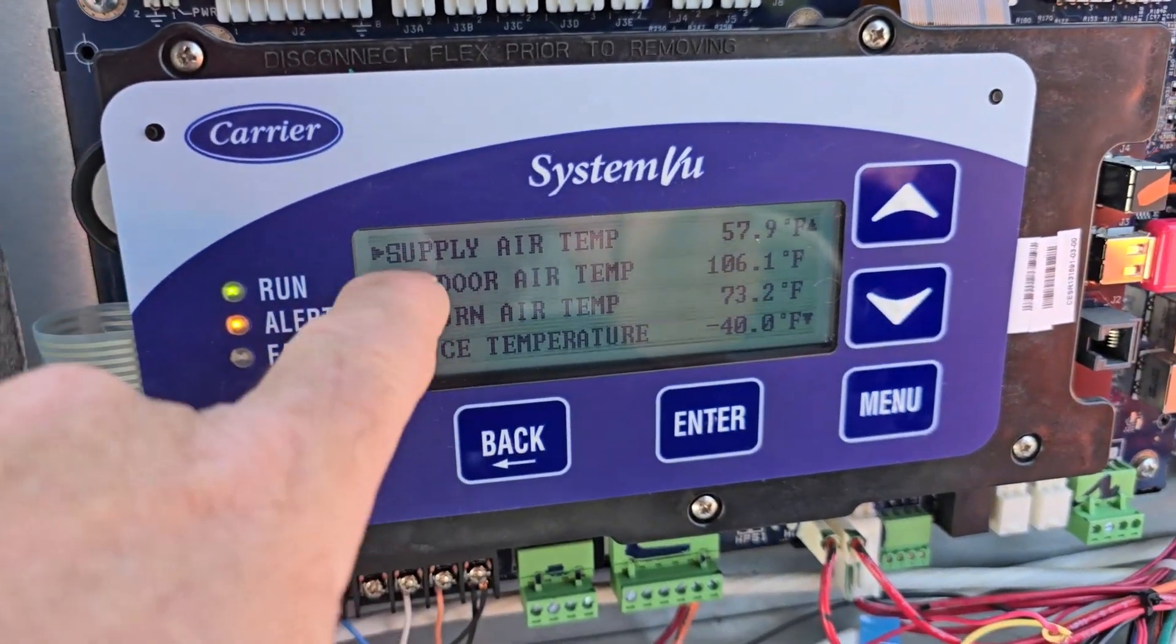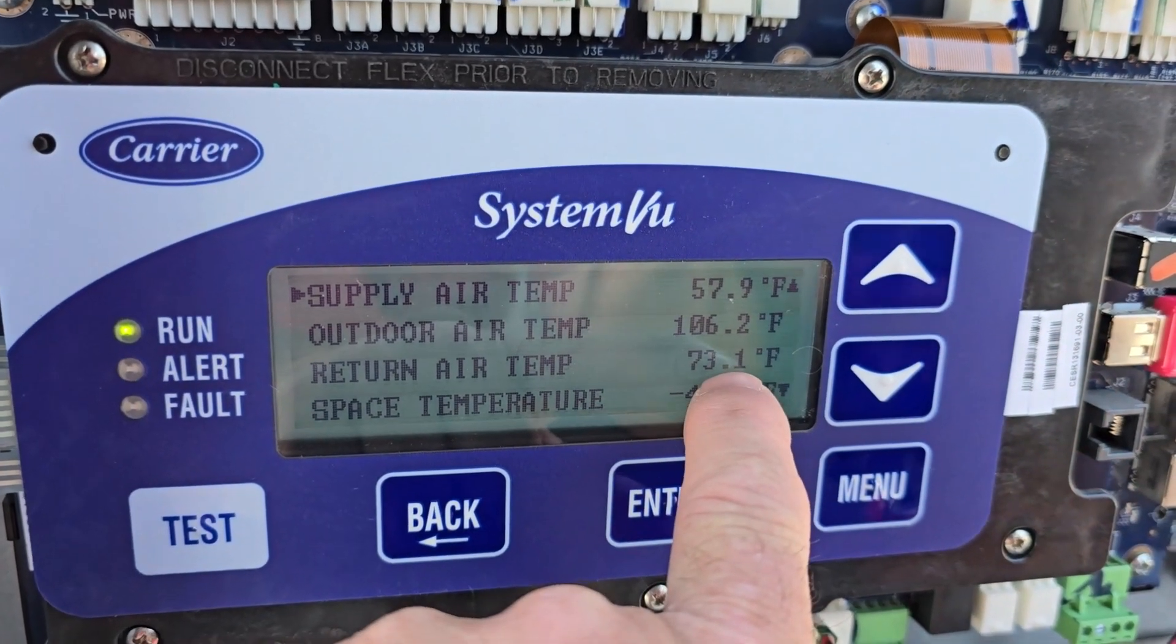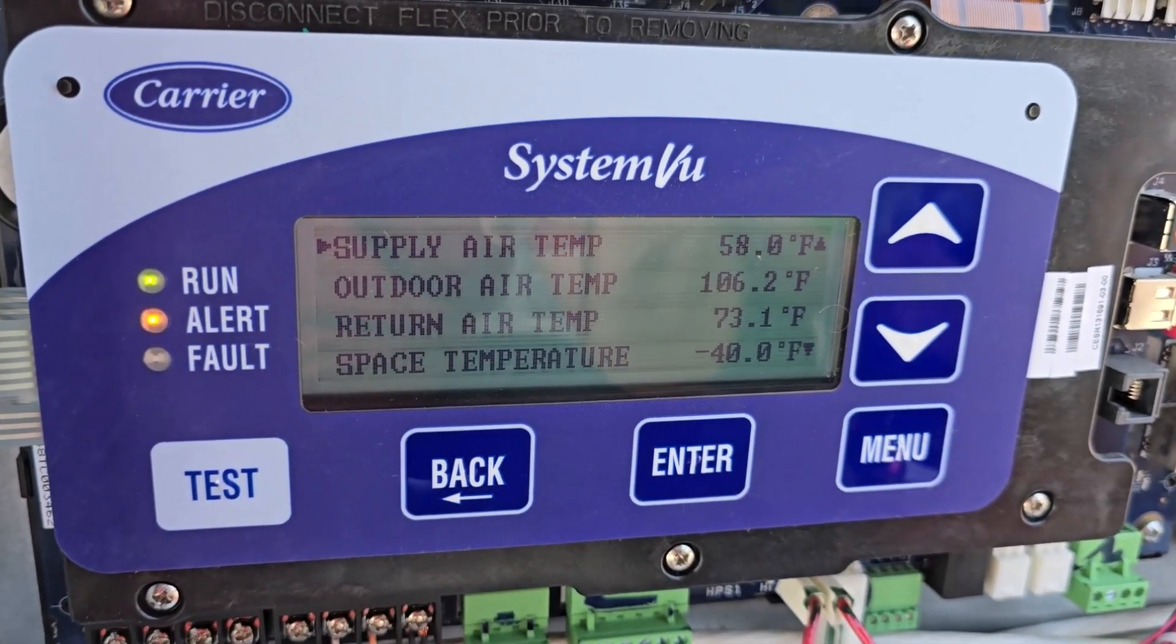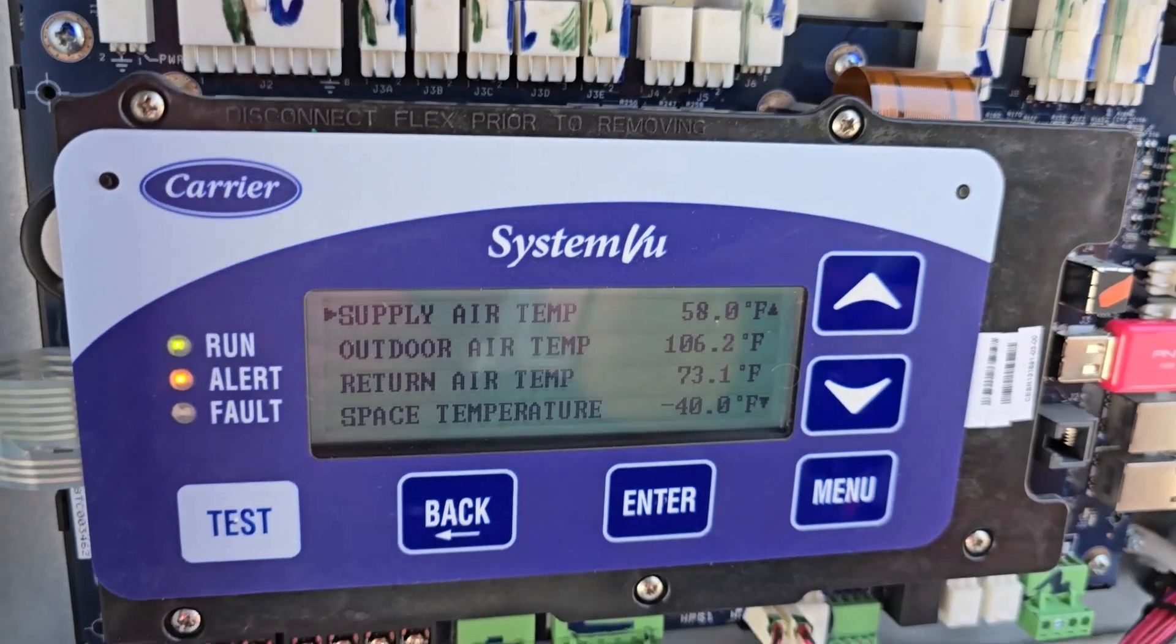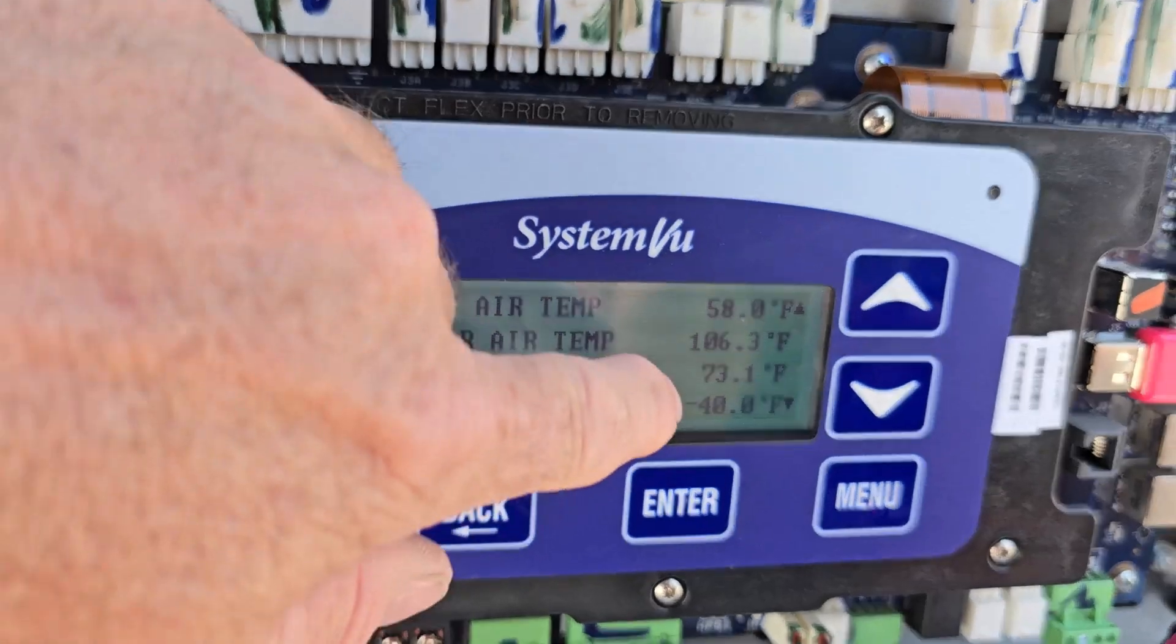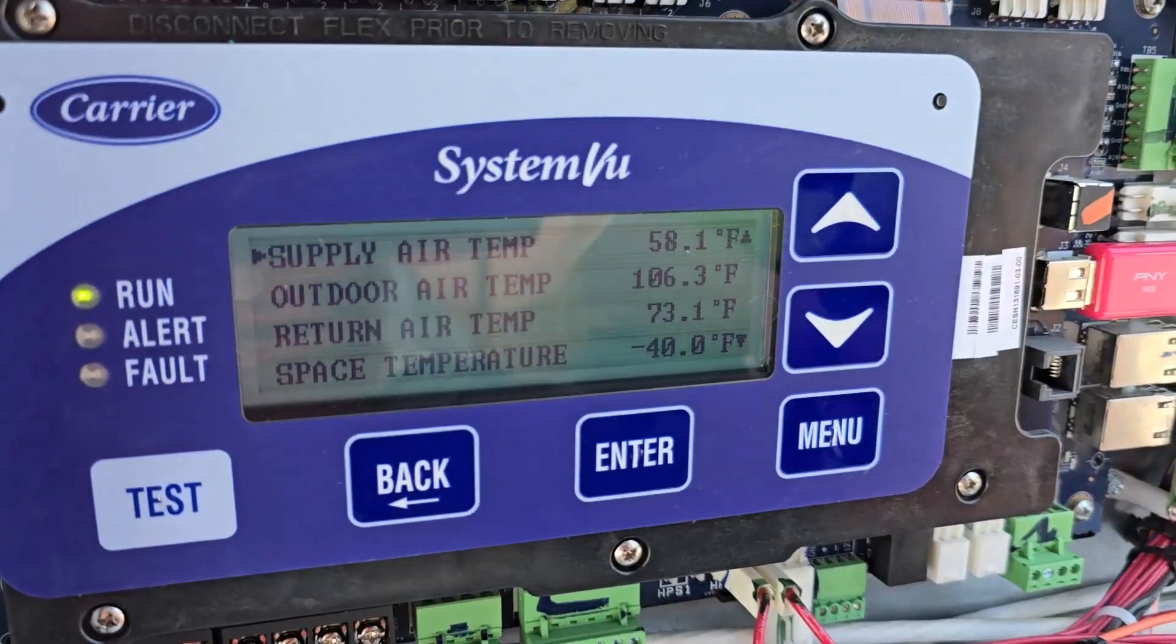One thing to note on these temperatures right here that we're just looking at is that this return air, which is the space temperature coming up to it, it's already dropping down to 73.1. That is read below the economizer damper. Just coming up to the duct connection. So then we have a 20% damper position right now for outside air. So we're mixing 20% of this 106 degrees. So it's probably closer to 80 at the coil. So 80 down to 58 is a 22 degree split. So it's actually doing really well.